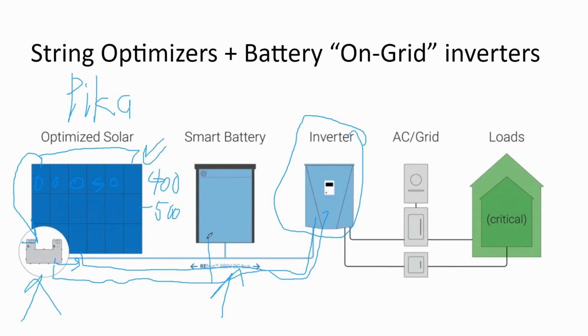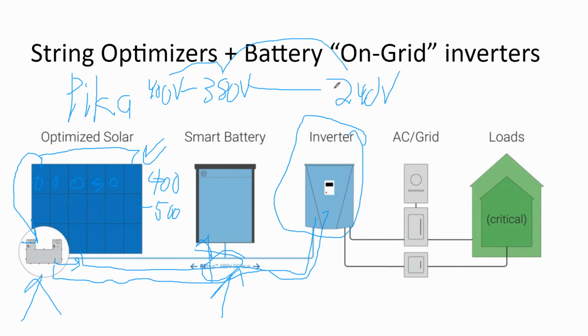Then they tap onto this DC bus a higher voltage battery bank. As far as efficiency goes, it's a very efficient system, as is the SolarEdge battery, because you're going from about 400 volts of solar down to a 380 volt battery, down to a 240 volt AC output. The closer these voltage ranges are to each other, the more efficient that energy conversion is going to be. Compare that to a solar array going from maybe 400 volts down to 48 volts and then back up again to 240 volts.